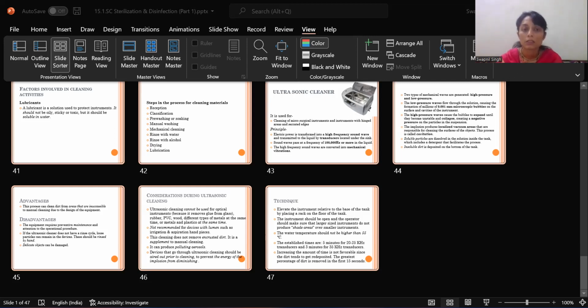Now coming to the detergent. The main considerations to keep in mind for choosing an appropriate detergent are: follow the manufacturer's recommendations for the type of dirt against which the detergent is supposed to be used. Then follow the manufacturer's recommendations about the device or instrument to be cleaned. If a mechanical cleaner such as an ultrasonic cleaner is used, the recommendations provided with the device as well as the detergent have to be followed. Then take into account the degree of water hardness. Now moving over to lubricants. These are solutions used to protect the instrument. They should not be oily or toxic, but soluble in water.